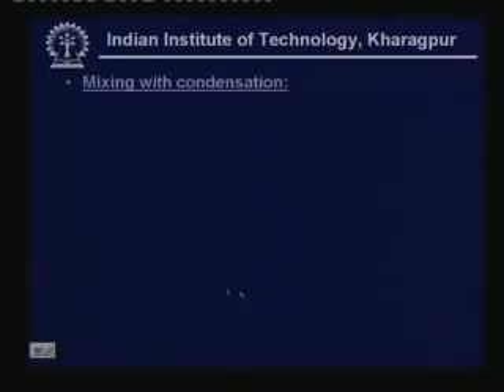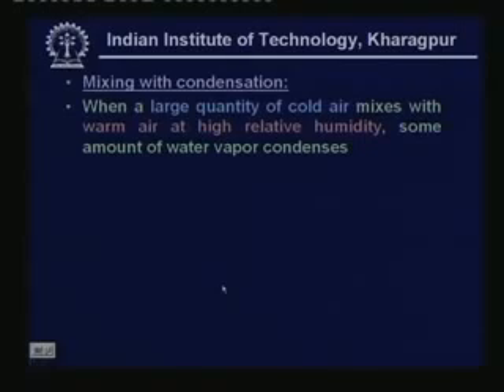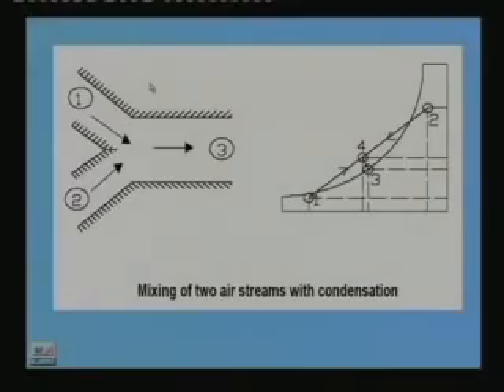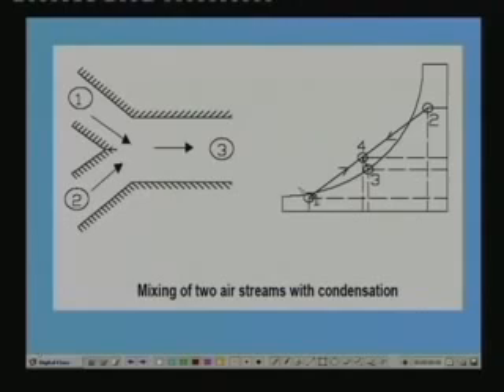You can also have a process called mixing with condensation. This happens when a large quantity of cold air mixes with warm air at high relative humidity. Some amount of water vapor condenses. For example, you have a special case, again a mixing process. Let us say that incoming air 1 is very cold, temperature is very low. This cold air is mixing with hot and humid air, that means point 2. The mixture condition must lie on the straight line joining these two points.